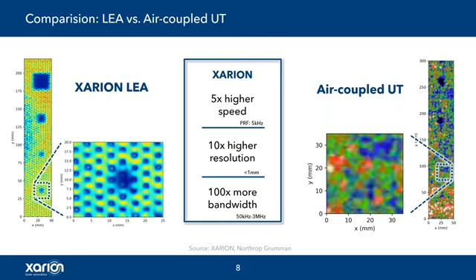But it's not only the resolution, it's also the speed. We can have up to 5 kilohertz of pulse repetition frequency. So obviously it means high speed. And last but not least, a very high frequency bandwidth. So in one scan, you capture the entire frequency bandwidth expanding from 50 kilohertz up to 3 megahertz. So you don't have a center frequency, but you have really a broadband signal. And then after the scan, you can decide whether you want to apply a digital filter and look for a specific feature at a specific frequency. So it captures all at the same time.